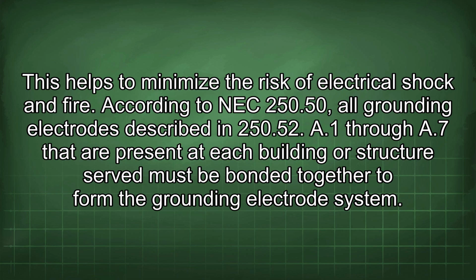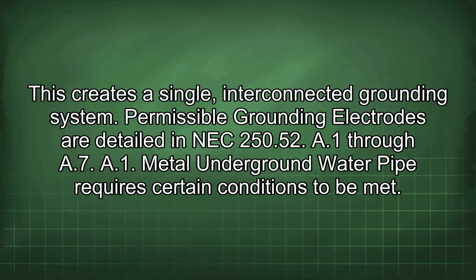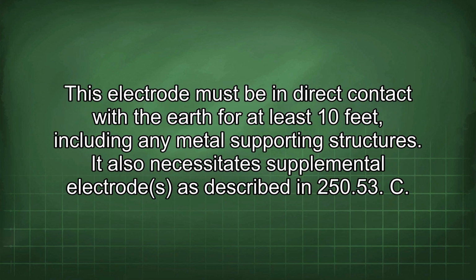According to NEC 250.50, all grounding electrodes described in 250.52 A1 through A7 that are present at each building or structure served must be bonded together to form the grounding electrode system. This creates a single, interconnected grounding system. Permissible grounding electrodes are detailed in NEC 250.52 A1 through A7. A1. Metal underground water pipe requires certain conditions to be met. This electrode must be in direct contact with the earth for at least 10 feet, including any metal supporting structures. It also necessitates supplemental electrodes as described in 250.53.